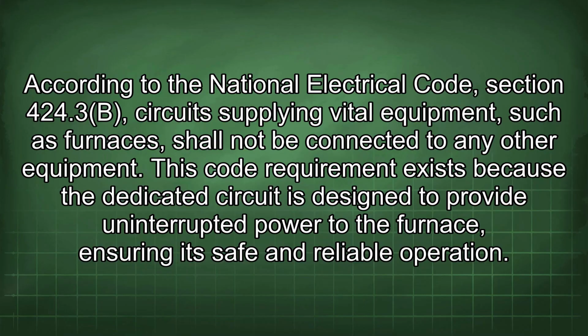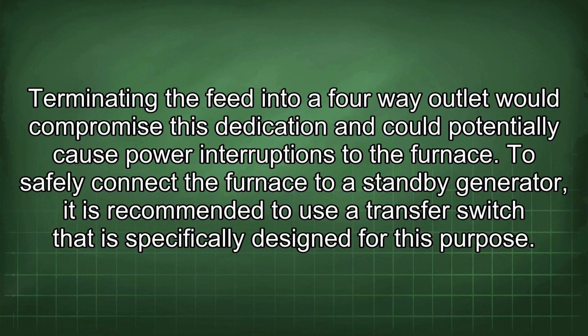According to the National Electrical Code, Section 424.3(B), circuits supplying vital equipment, such as furnaces, shall not be connected to any other equipment. This code requirement exists because the dedicated circuit is designed to provide uninterrupted power to the furnace, ensuring its safe and reliable operation. Terminating the feed into a four-way outlet would compromise this dedication and could potentially cause power interruptions to the furnace.